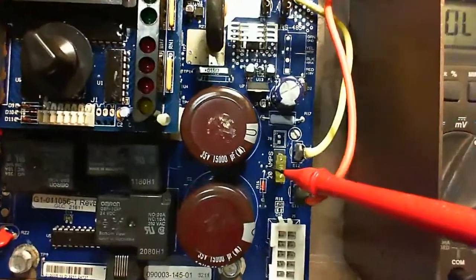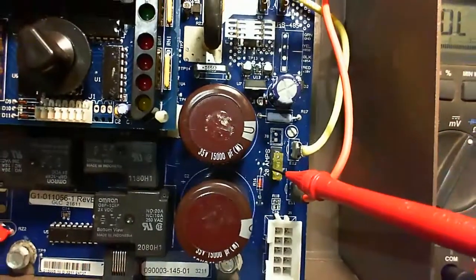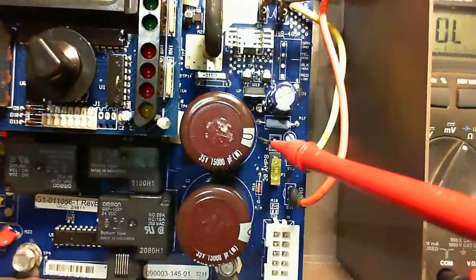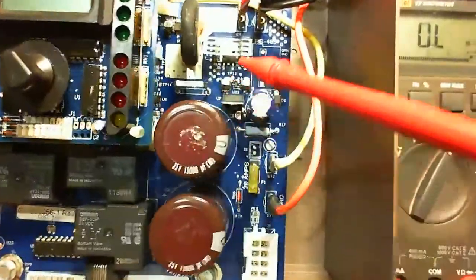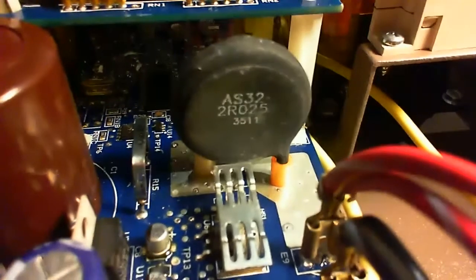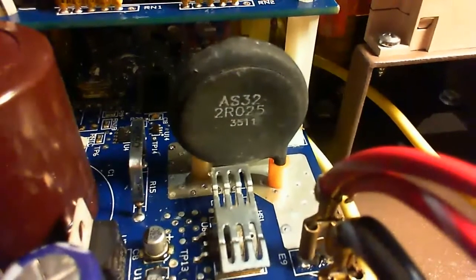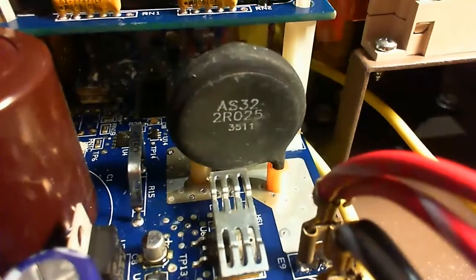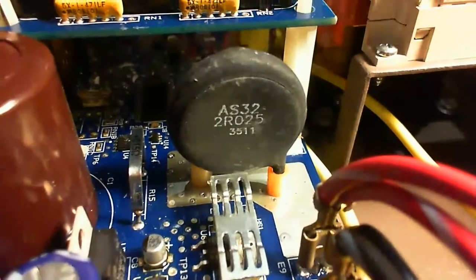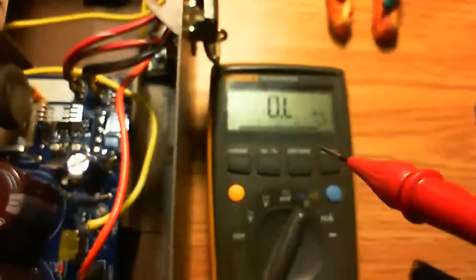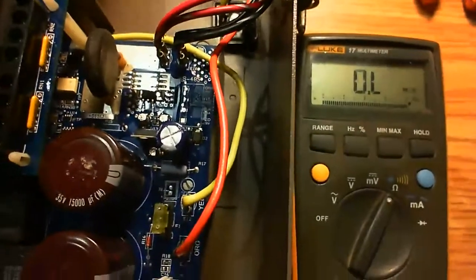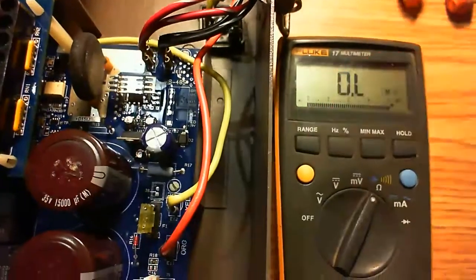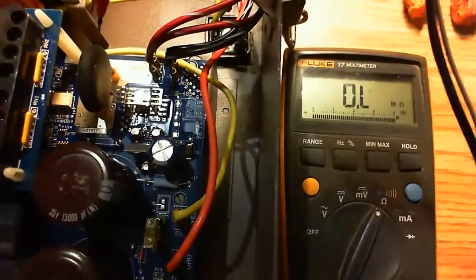There's not much we could check on this board except for the relay contacts and coils maybe. This board has at least two layers and they put conformal coating everywhere for protection. One thing that caught my eye was this big black component here. It's an inrush current limiter also known as an NTC thermistor.